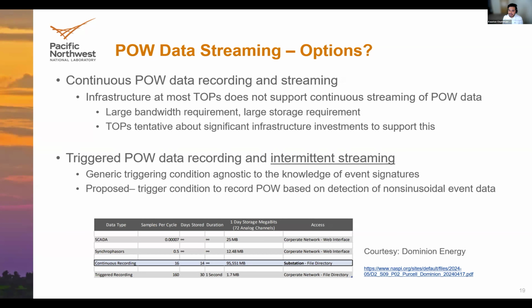Instead, as we've already been doing, there's triggered point-on-wave data recording. But one caveat is that the triggering condition has to be agnostic to knowledge of the event signatures - it has to be more generic, so you can record a larger set of events without exactly knowing what you want to record.